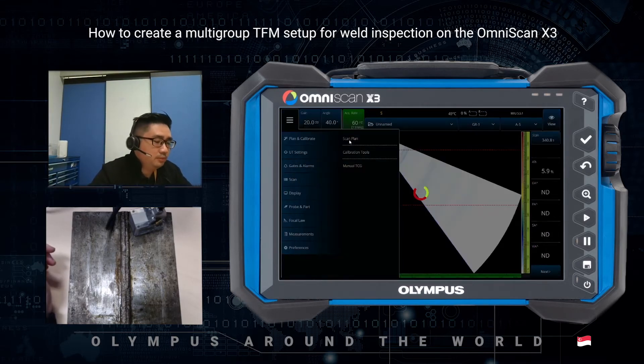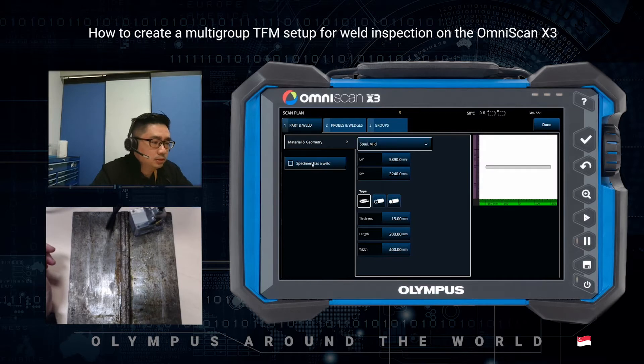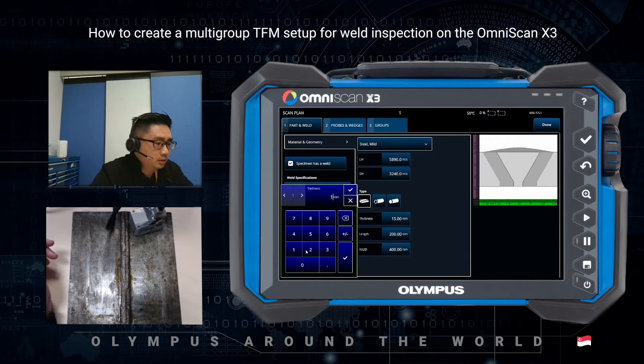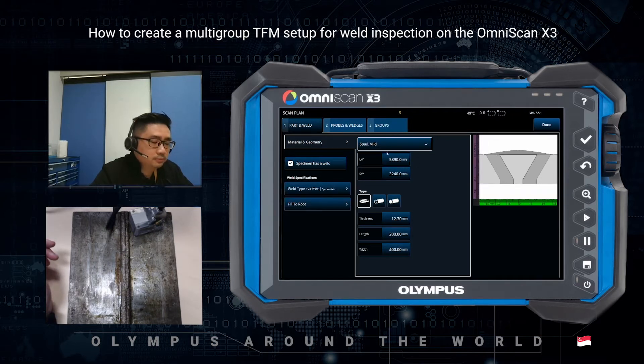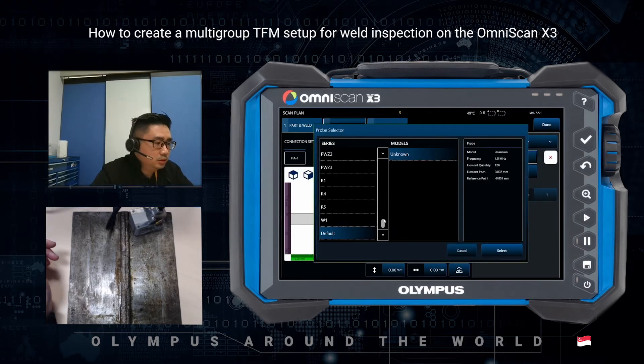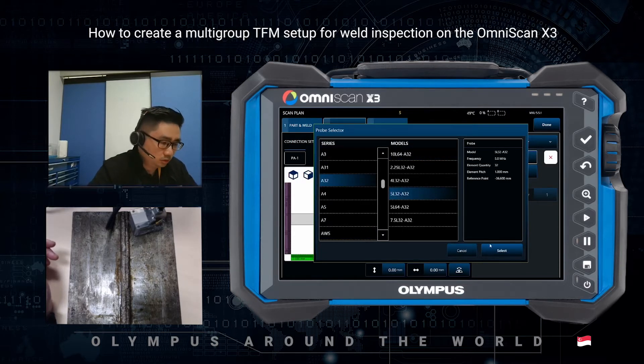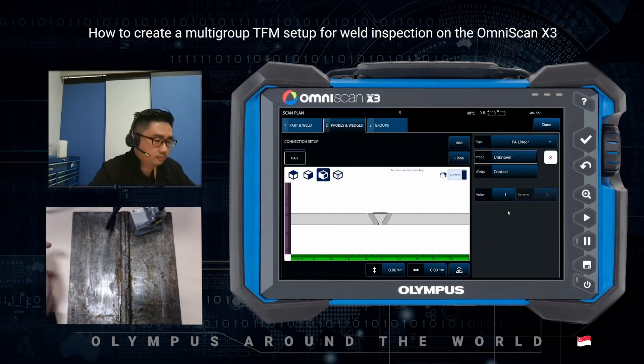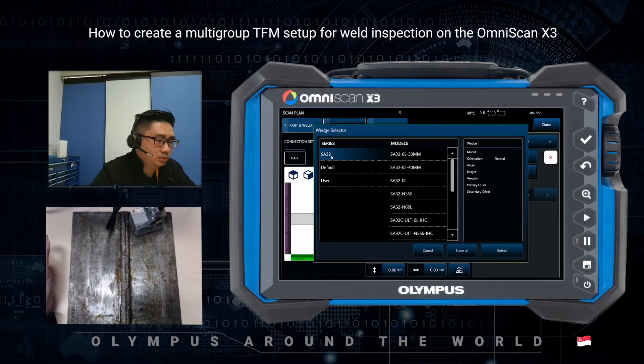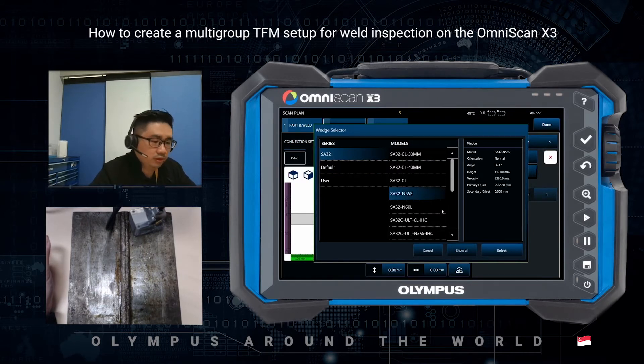Go to the scan plan. This is a weld — half inch, or 12.7mm. We choose our probe, the A32, 5L32A32. Select. Then we choose the wedge. You can see that the SA32 is automatically selected when you choose the probe. This is an N55S wedge.